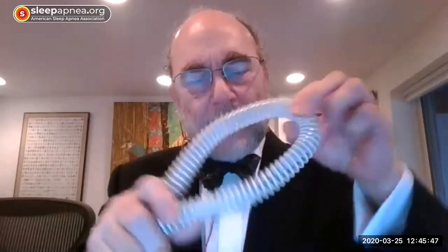To address that, I'd point out that most ventilators used in hospitals today are so-called dual circuit or closed circuit ventilators. The patient is on one end, and there are two tubes that go back to the ventilator—inhaled air goes in one, exhaled air goes out the other and gets captured, filtered, and usually goes through a CO2 absorber if used in the operating room or similar setting.